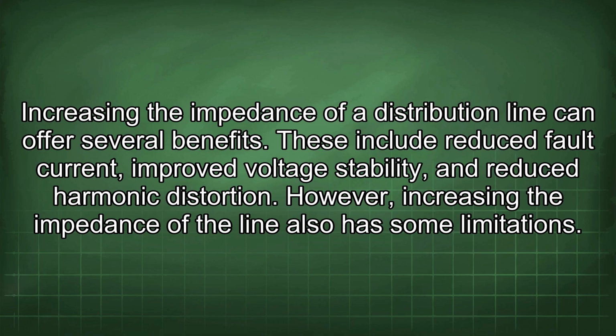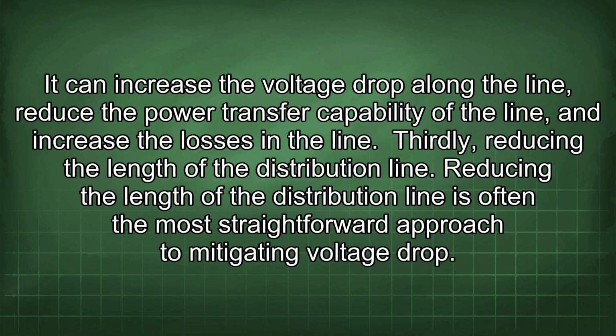However, increasing the impedance of the line also has some limitations. It can increase the voltage drop along the line, reduce the power transfer capability of the line, and increase the losses in the line. Thirdly, reducing the length of the distribution line. Reducing the length of the distribution line is often the most straightforward approach to mitigating voltage drop.